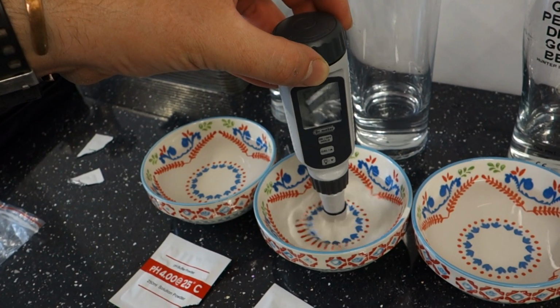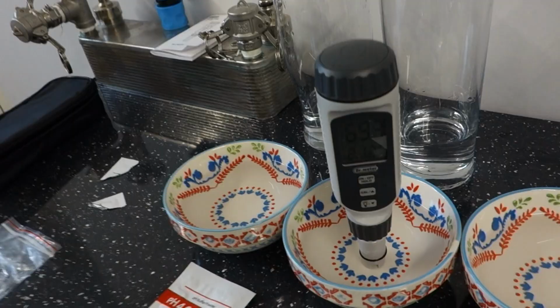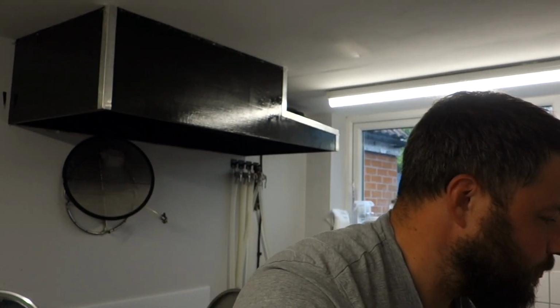Now let's try this middle one again. See if we get a better reading this time. 6.88. That's not bad. That's not bad. I think that's pretty good. Let's have a look at what the accuracy is. Yeah, measurement stability 0.03. We're calibrated on the pH meter, which is good. In fact, it's just gone to 6.86. Yeah, that's good. I'm happy with that.